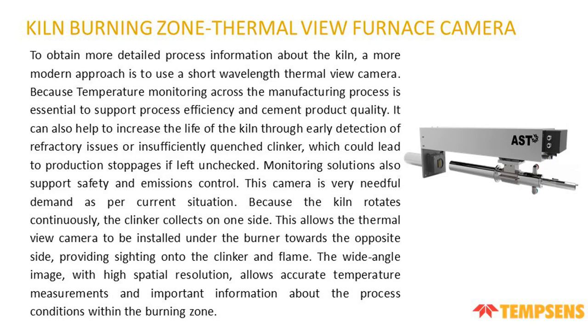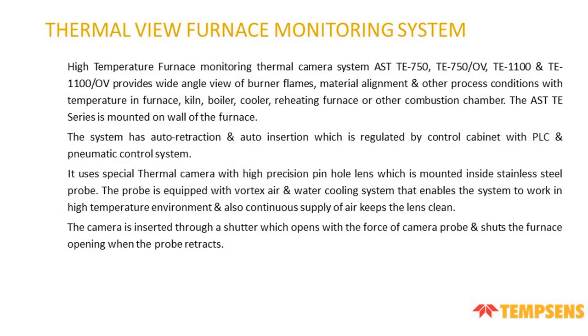This camera is in great demand in the current scenario because the kiln rotates continuously and the clinker collects on one side. This allows the thermal view camera to be installed under the burner towards the opposite side, providing sighting onto the clinker and flame. The wide angle image with a high spatial resolution allows accurate temperature measurement. High temperature thermal view furnace monitoring system. The high temperature furnace monitoring thermal camera systems AST TE-750, TE-750 OV, TE-1100, TE-1100 OV provide a wide angle view of the burner, flame, material alignment, and other process conditions with temperature.